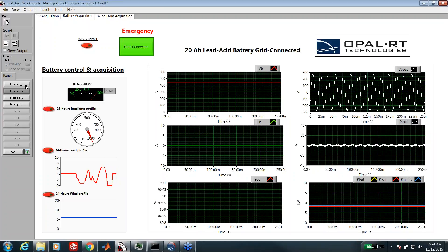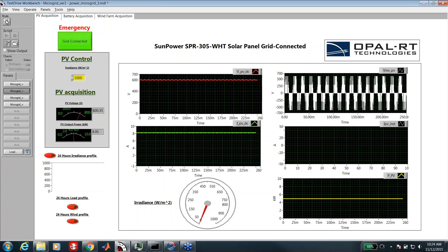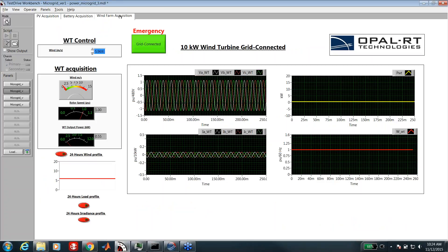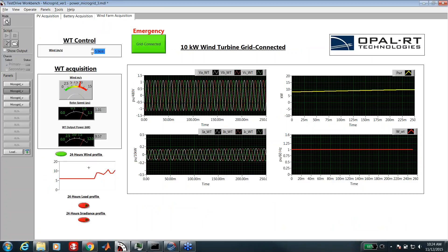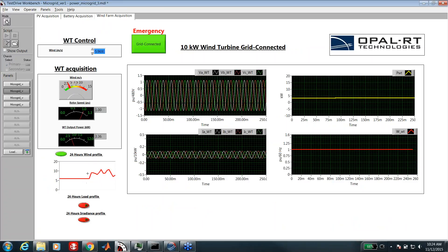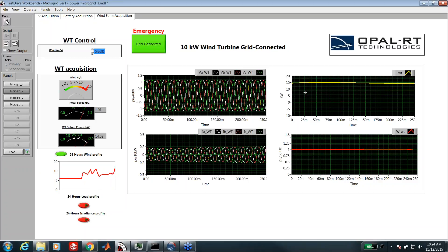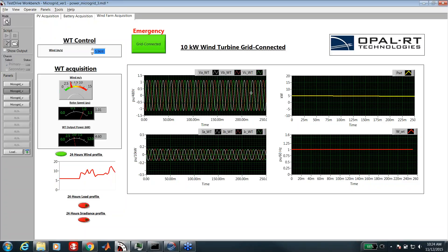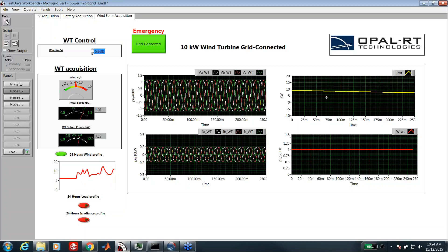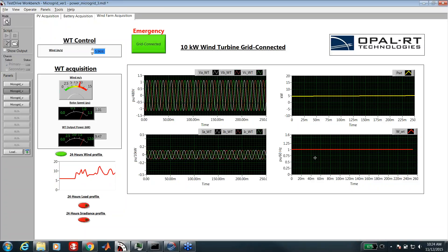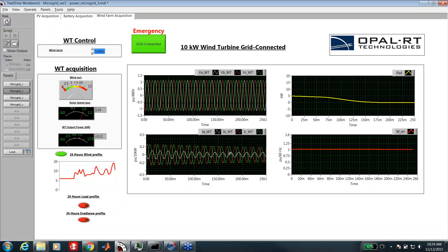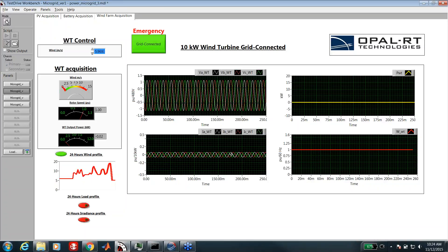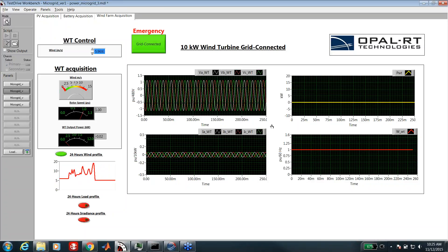For the wind turbine, we can do many tests. I am showing only the principal tests, but we can do many other tests on the PV, battery, or wind turbine side. Here I am applying a 24 hours wind profile. We can see the behavior of the wind turbine: the voltage, the current, the power, and the speed of the rotor. This kind of test can be used to validate the model simulation of the wind turbine by applying these profiles and comparing the results with experimental results collected from real life.